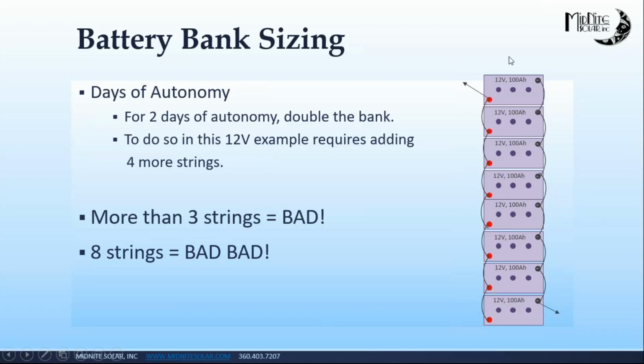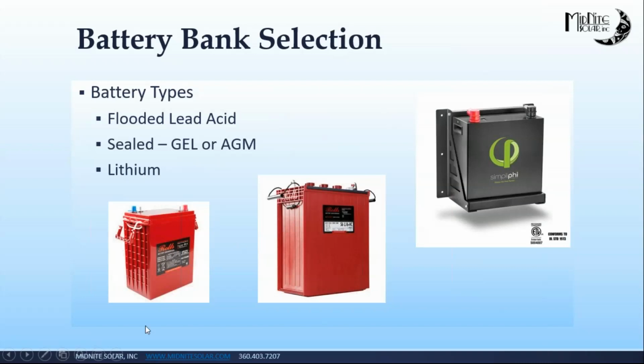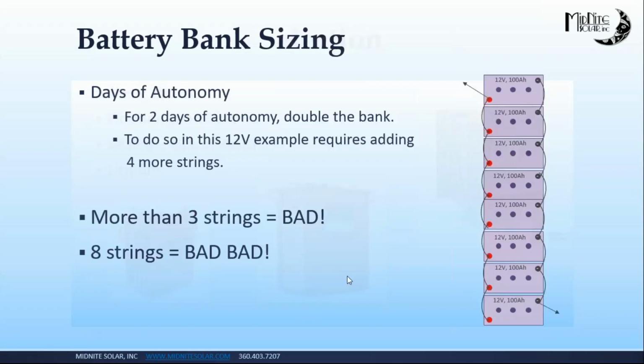That's why, if you design this today, you identify your total energy needs and your future growth, then design the system today with 6 volt batteries or 2 volt batteries. For example, if you had 2 volt batteries, you'd have a single string, and you could add 2 more strings. That's a tremendous amount of capacity. A 2 volt battery is on average about 1,100 to 1,300 amp hours.